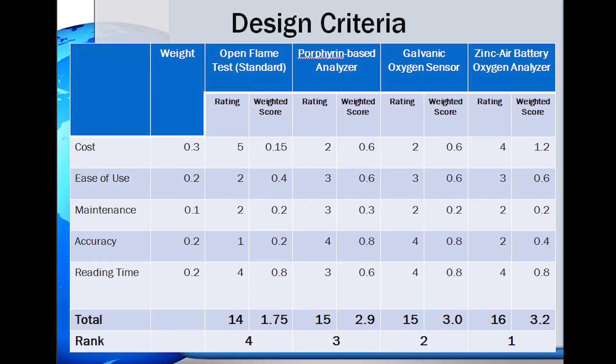Three current solutions were compared against our solution using a Pugh matrix. After our initial research, the team developed a list of five criteria that factor into the design of a successful product. We decided that driving down cost was the primary improving factor that we could target, followed by equal shares of accuracy, ease of use, and reading time. The last is the ease of maintenance. The results put the zinc air battery design at the top, followed by the galvanic oxygen analyzer, the porphyrin-based analyzer, and lastly the open-flame test.